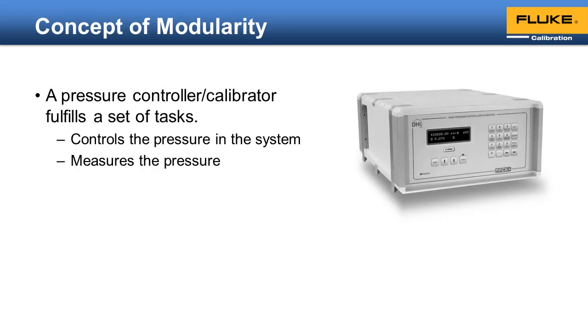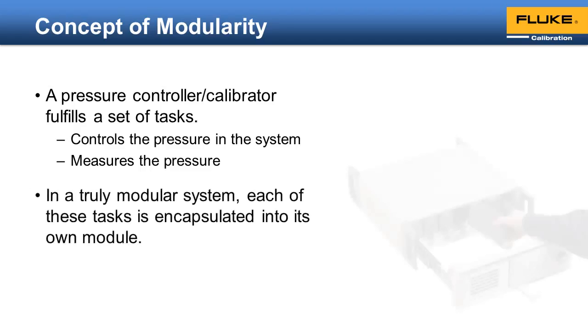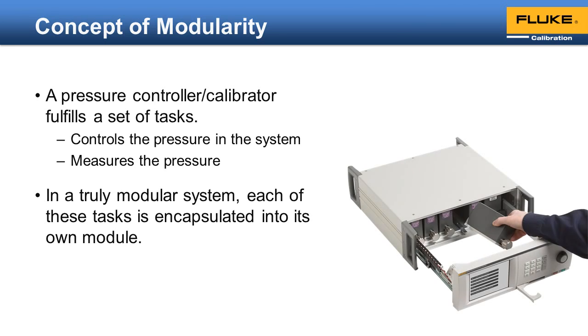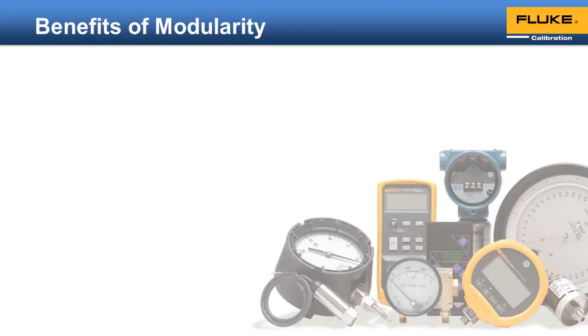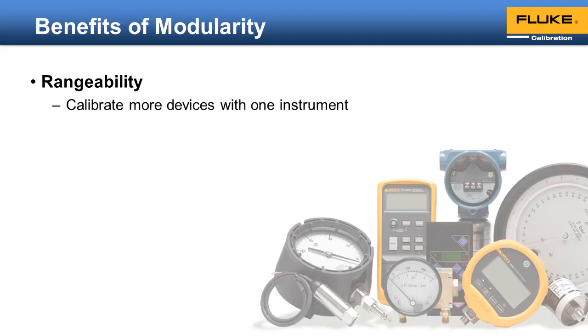In a traditional non-modular design, the internal components that perform each of those tasks are closely intertwined. With a modular system, each task is encapsulated into its own module. Why have a modular design? Modularity provides a number of benefits to the operator. First is rangeability. If your pressure controller has modules with different pressure ranges, you can calibrate more devices than if it has only one, fixed range that cannot be changed.